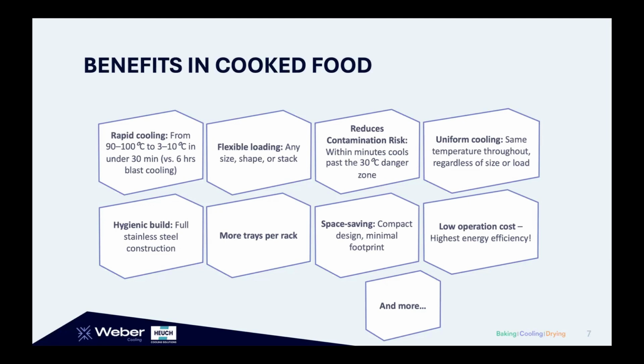The uniform cooling, as we explained, is due to the equal pressure in the room. And there's also low operation cost — vacuum cooling is very energy efficient compared to a blast chiller, because of the chiller, the cold trap, and the very fast cooling times.